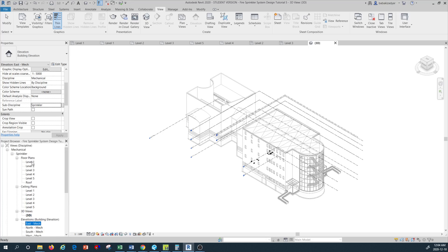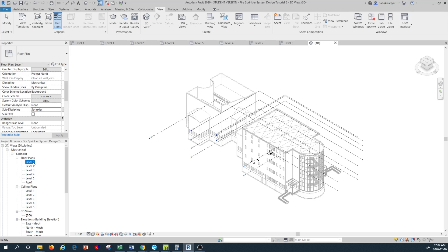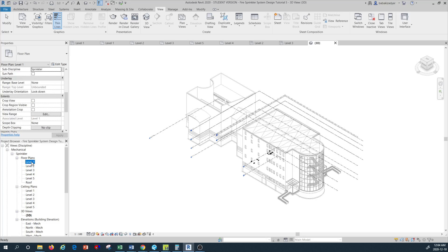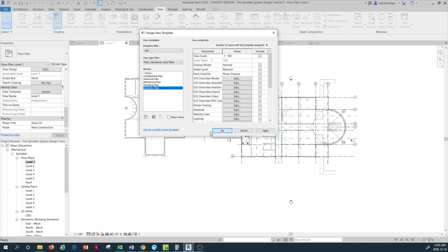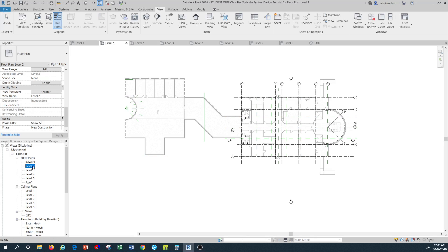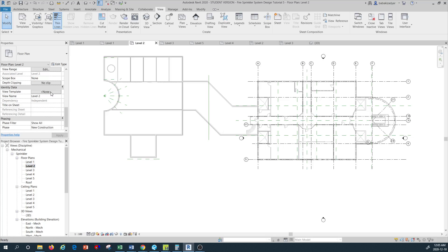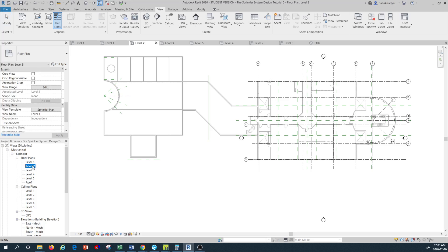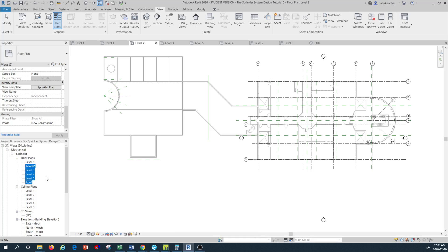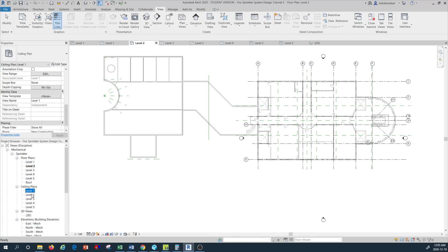We also need to make sure all our levels have the same view template, because they need to be consistent with the Sprinkler view template we just created. I go to Level 1, click on it, and see what template it has — I change it from None to Sprinkler Plan. Then Level 2. You can do this one at a time, or select all levels by holding Control and apply the Sprinkler Plan view template to all at once.